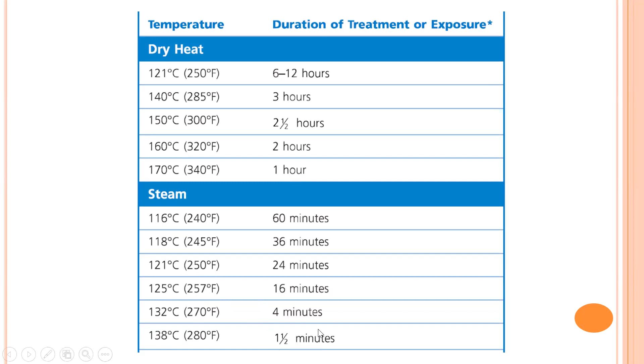So that is the biggest advantage of the autoclave, because it helps penetrate the heat through moist steam into all instruments. It spreads uniformly and also kills the organisms, including spores, in a very short time. There are even some autoclaves that use very high temperatures. At 138 degrees Celsius and under pressure, it just requires a minute and a half to sterilize instruments. So in big hospitals, when they require a rapid turnover of instruments, they need a quick autoclave. They have very small autoclaves which can operate at these high temperatures, and they can do rapid cycle autoclaving to give you the instrument sterilized.